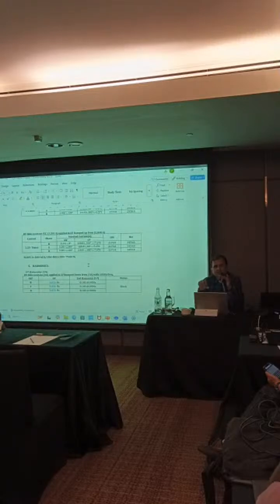This is the other way to test the differential relay without template. So now you have learned three ways to test differential relay. Manual mode, you do not require any software, even if local control is there, you can test the differential relay with all these details. And the second, if a template is there, just enter the settings of the relay and create template and run the test, which we are going to do now.